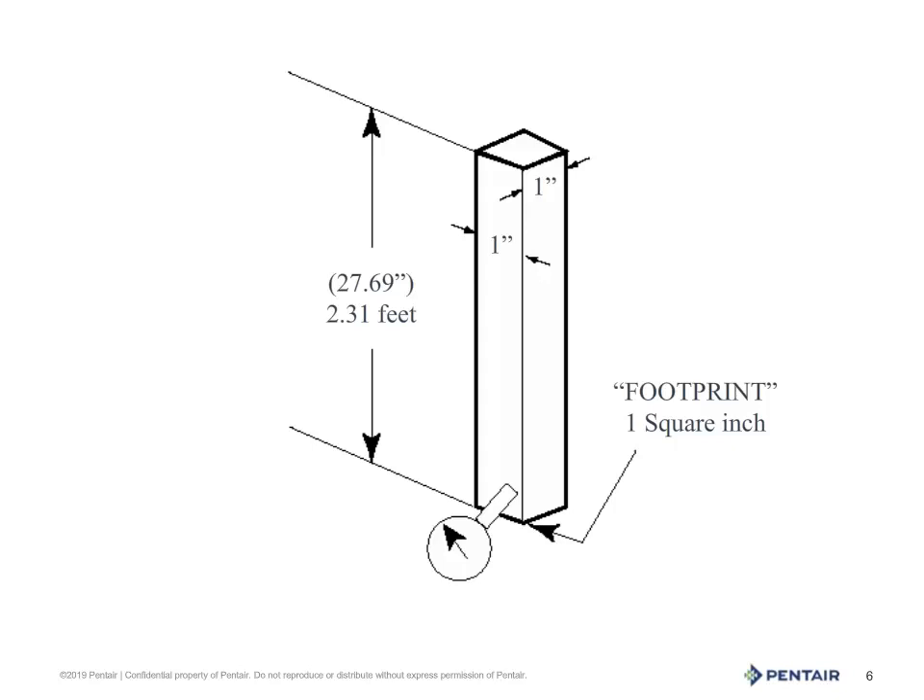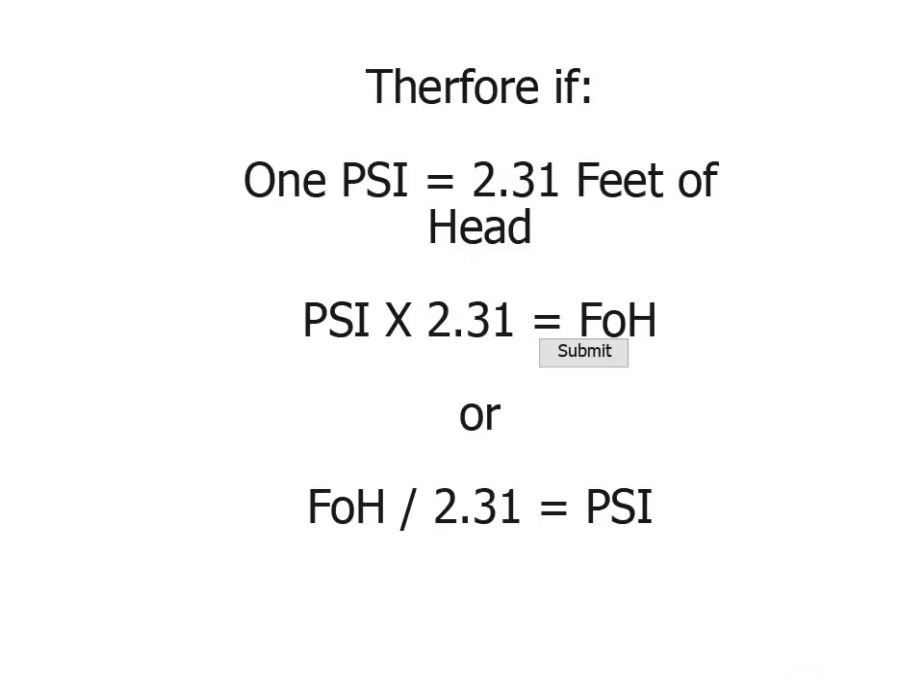I'm glad you asked that question. 0.433 pounds is not what we usually use, because in our industry we work in whole psi. So if we take 1 and divide it by 0.433, we get that magical number of 2.31. Now I can see you're still not impressed, so let's go on. What this means is 1 psi is equal to 2.31 feet of head.